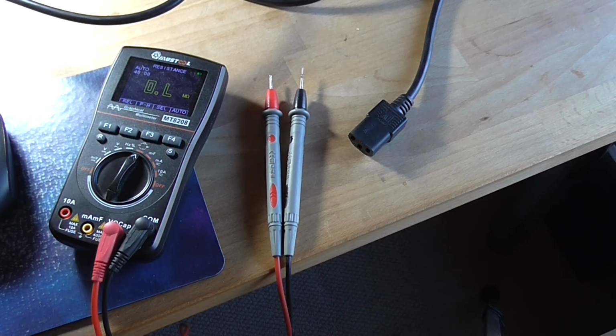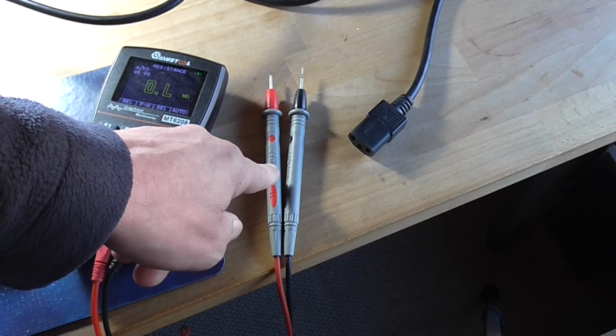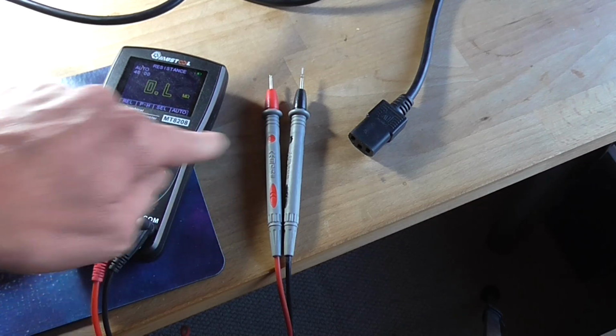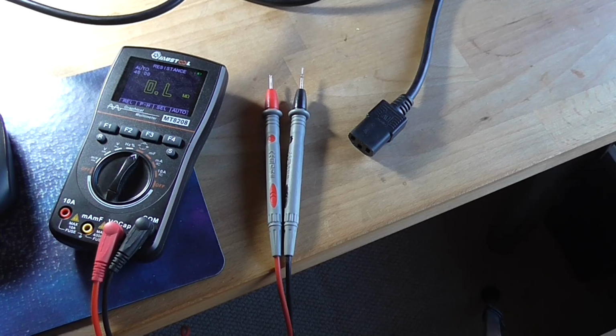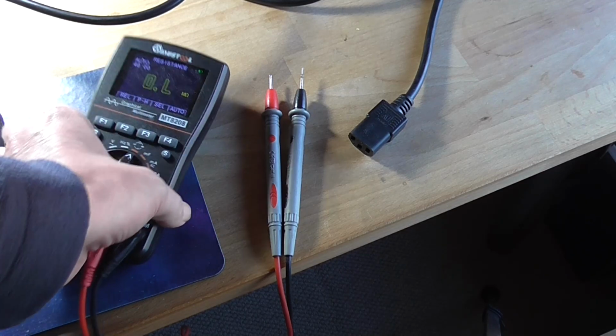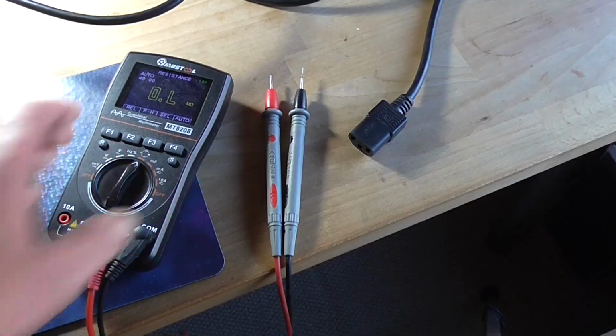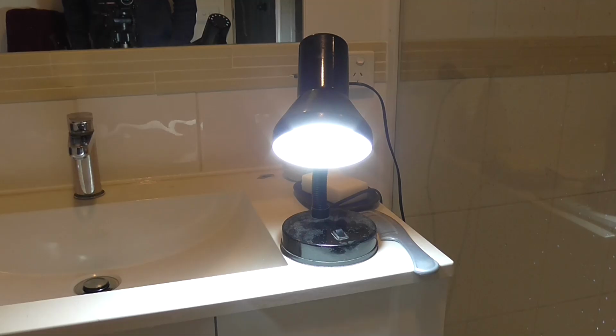And that is the reason why I say do not try this test at home, because if you connect the multimeter probes with the resistance reading across earth and live, well, bad things can happen, like blowing up the multimeter and tripping the circuit breaker. And please don't use electrical devices whilst taking a bath. And it's not guaranteed that all houses actually have an RCD. That is something you would have to actually find out.